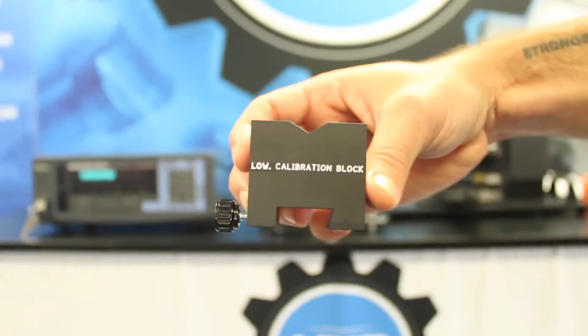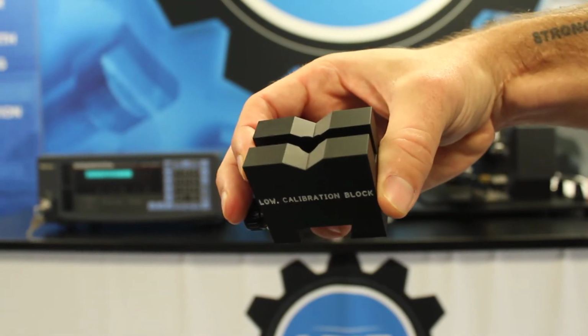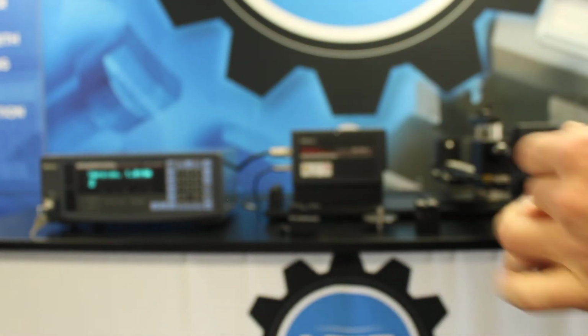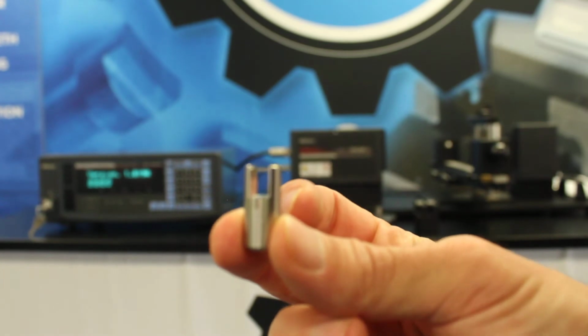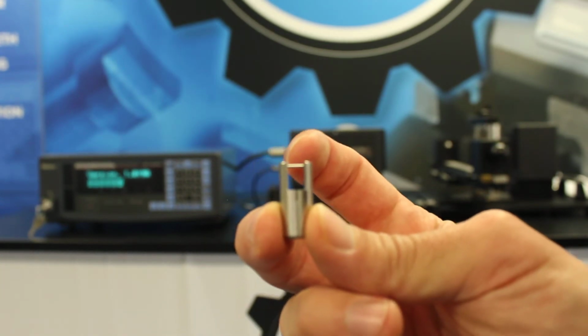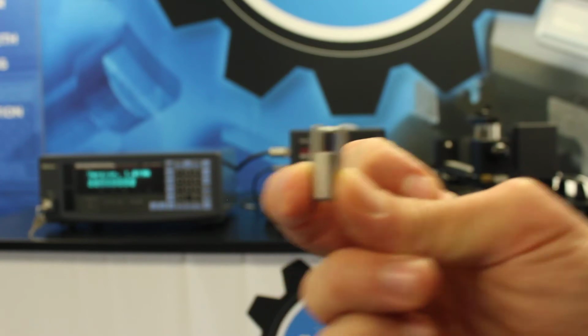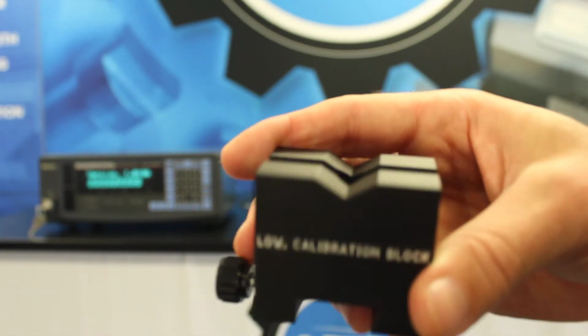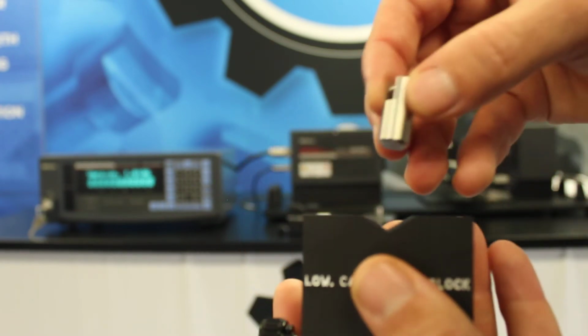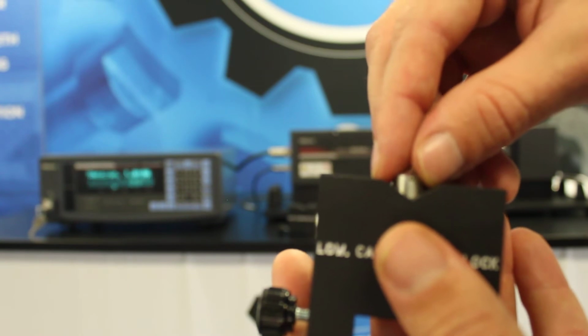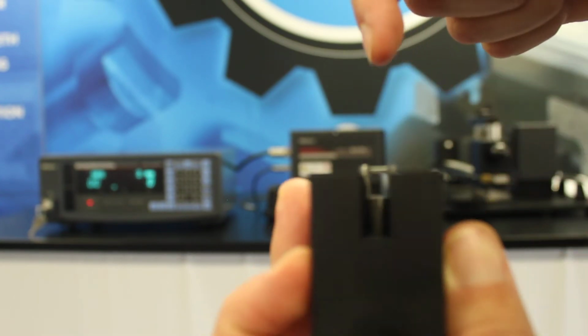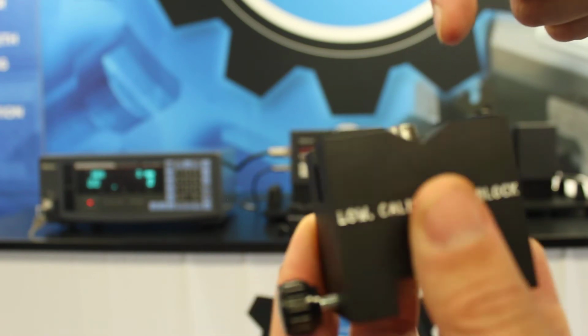First up is this low calibration block. You can see that this is marked low calibration block, and it does have a little recess in that V. That is for this low calibration artifact. The low calibration artifact is this little guy here, and the small pin that runs across the top is the actual artifact. When you install this into the block, the recess is where this will fit down into, and you want to make sure that the pin at the top is perpendicular to the receiving unit so that it is shooting across that diameter.